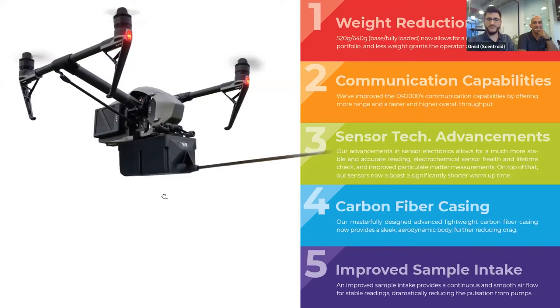Now here you can see the probe in the photo. That's the sample intake probe where the air flows in, providing the sample for both gases and particulate matter sensors, all included inside the housing. Unlike before, when we used a pump to take samples in, we're now using a fan to create negative pressure inside the box. The air flows in very smoothly through this probe, across the sensors, and out of the system. This way we reduce the pulsation caused by pumps, and therefore drastically reduce the noise from the sensors.